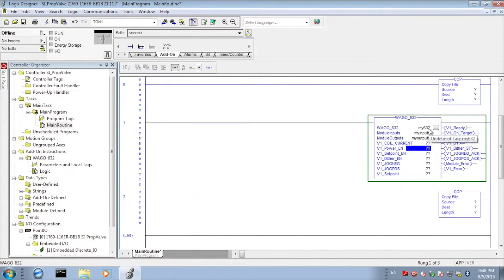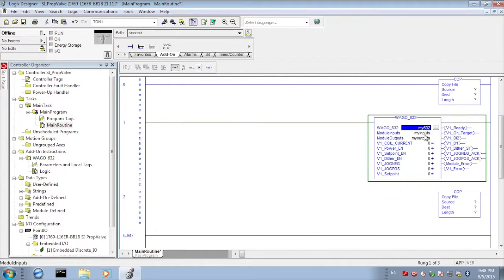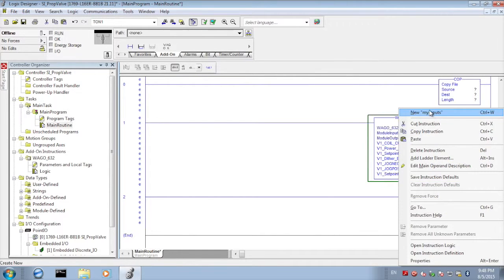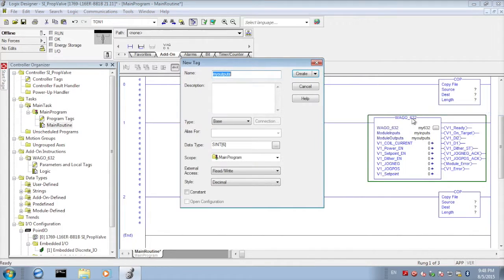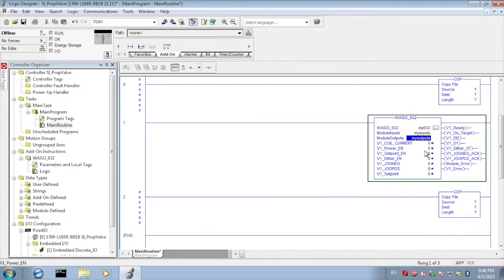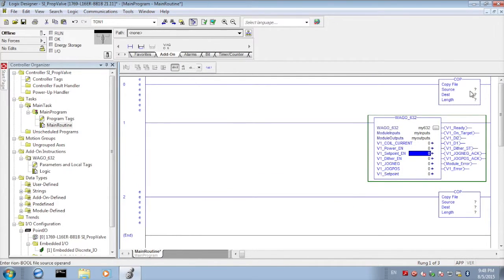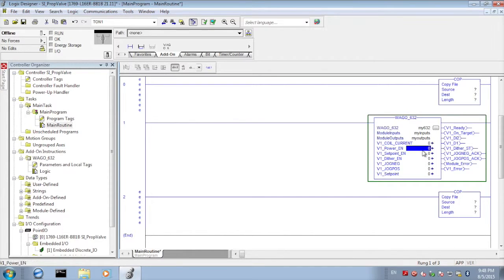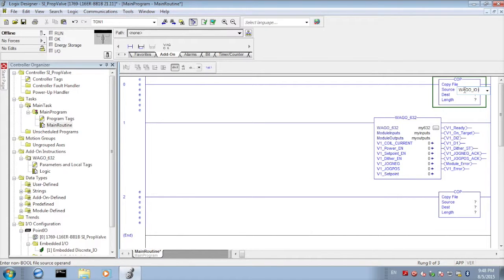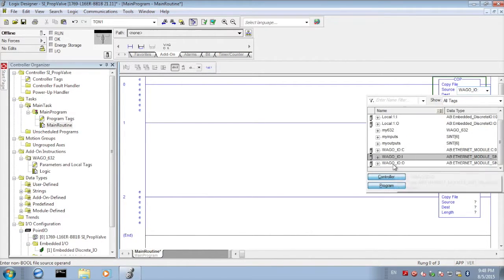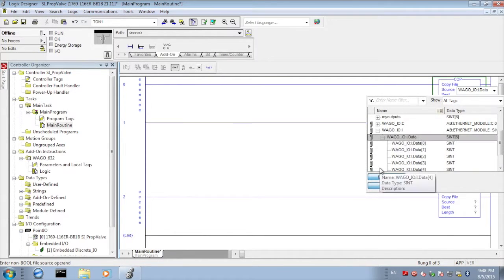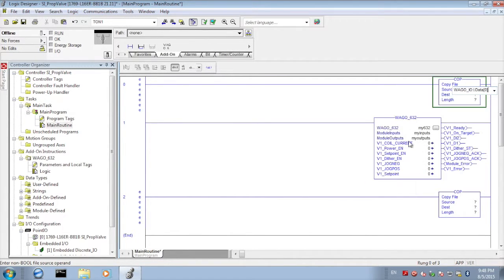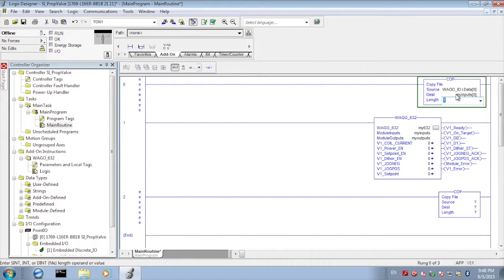Under inputs we'll make my inputs and my outputs and we'll just create those tags here. Next we'll move over to the copy blocks and what we'll want to do is copy the data from the remote IO into the add-on. So we'll select our WAGO input, input data, and we're going to start at sint0. Our destination is my inputs for the add-on instruction at the 0 byte and length is going to be 6.